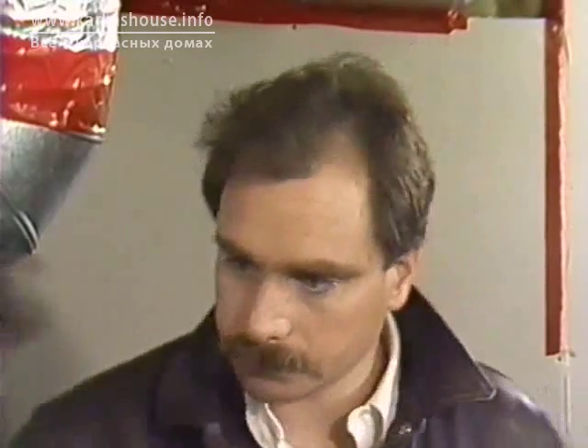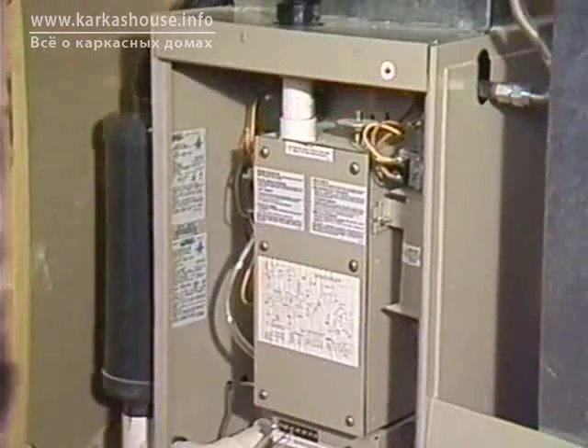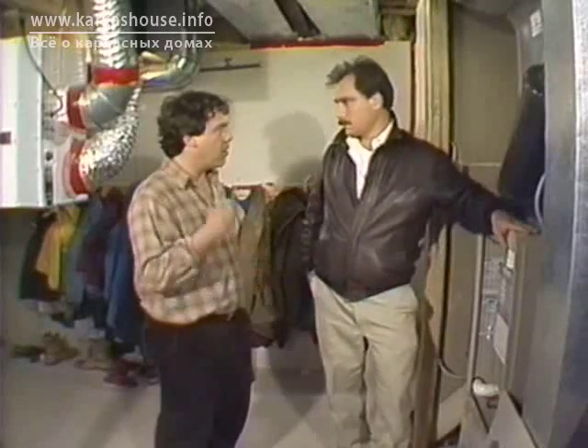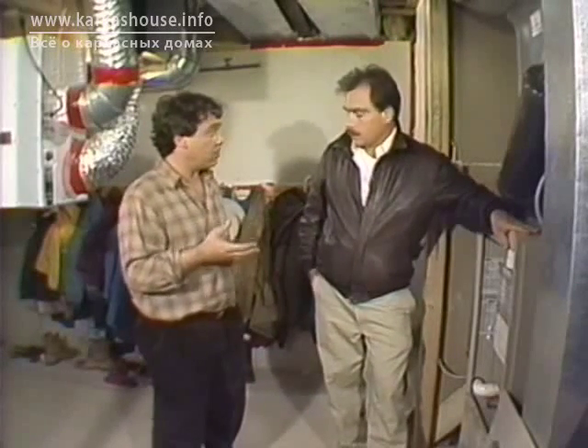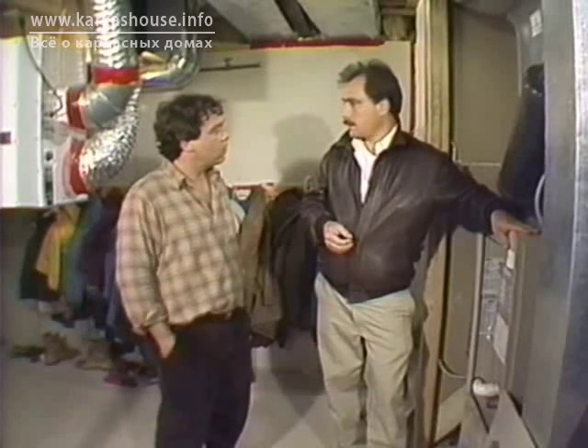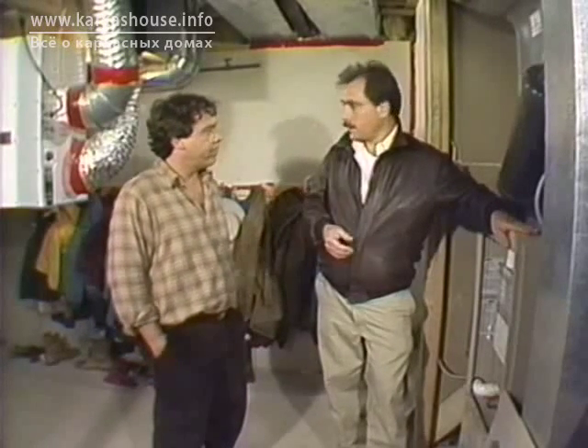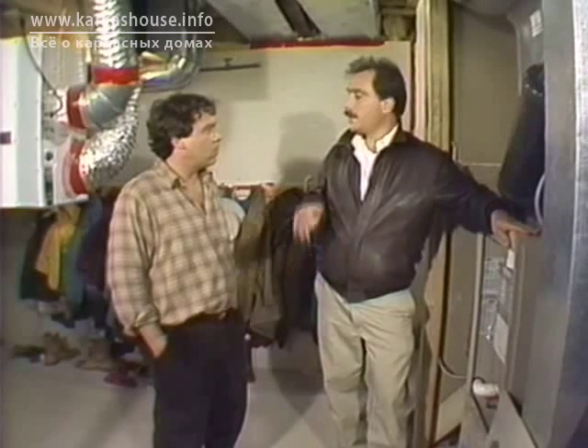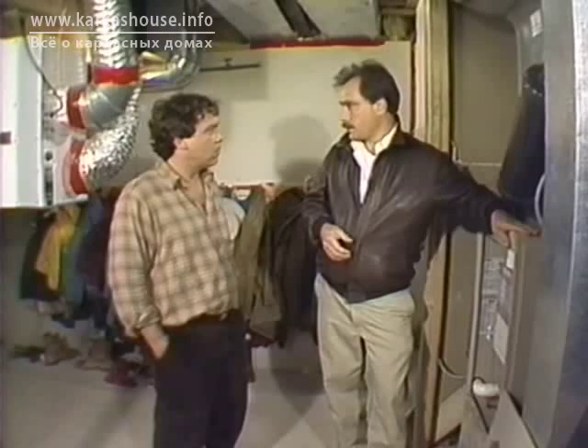Now, what we ought to do, if that's adequate for ventilation systems, is to take a look at mechanical systems, at the heating system of the building. So let's look at the fourth item that we were intended to cover. Okay. Are these new energy-efficient furnaces that are available part and parcel of the R2000 house? No, really the single most important criteria in selecting a heating system for an R2000 house is safety. Health and safety is the central issue. We want to ensure that there's no backdrafting and there's always a good supply of combustion air.